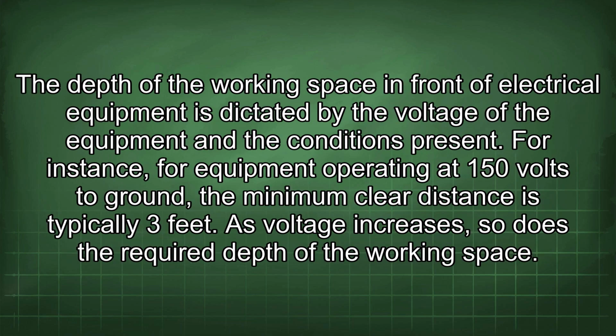The depth of the working space in front of electrical equipment is dictated by the voltage of the equipment and the conditions present. For instance, for equipment operating at 150 volts to ground, the minimum clear distance is typically 3 feet. As voltage increases, so does the required depth of the working space.